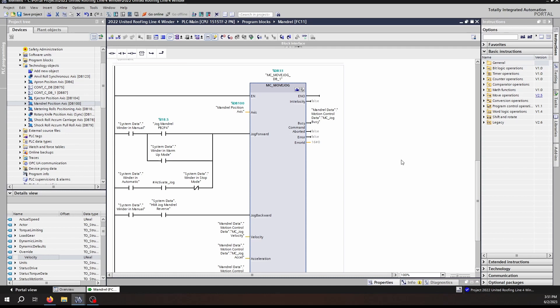We've already talked about the fact that there is a Jog Forward and Jog Backwards bit, which is almost similar to how the direction bit is on the MC Velocity. With that said, the MC Velocity is a single trigger, so for each time the execute bit activates the inputs and executes the move. The MC Move Jog does not operate that way.